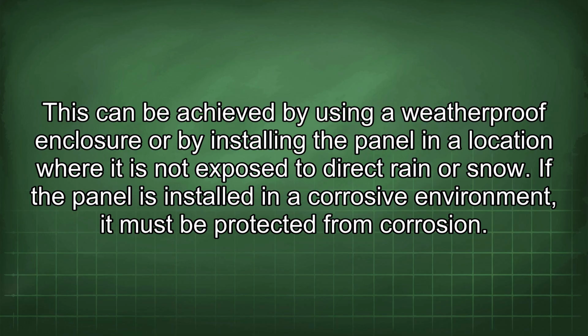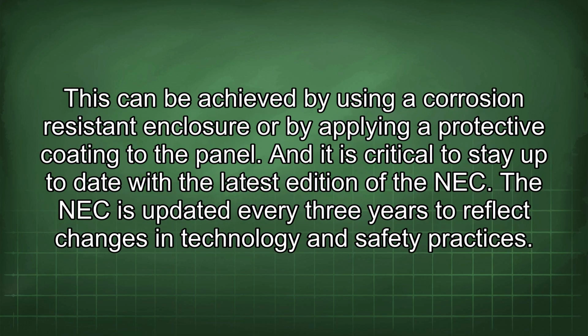This can be achieved by using a weatherproof enclosure or by installing the panel in a location where it is not exposed to direct rain or snow. If the panel is installed in a corrosive environment, it must be protected from corrosion. This can be achieved by using a corrosion-resistant enclosure or by applying a protective coating to the panel.